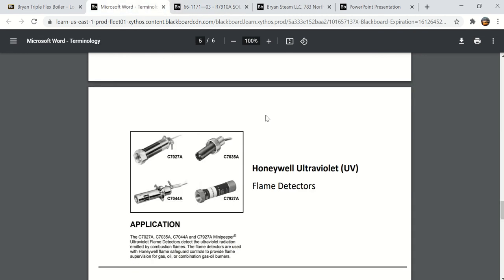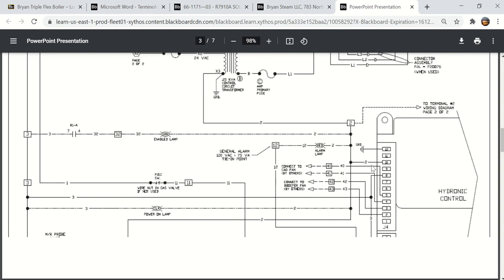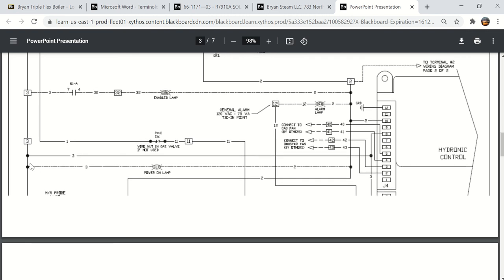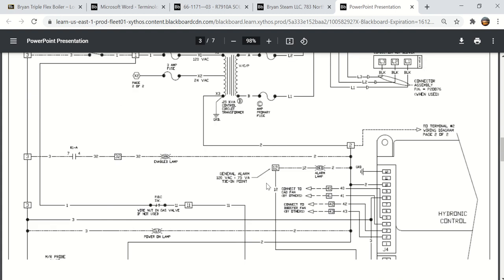All right, getting back to the drawing. There we go. Now I think we've covered pretty much everything that's connected to J4. We have our neutral, we have our ground, we have the power going in here for the UV, and then we have our switch connections here for the combustion air damper and the booster fan. Going on down, here's the power on lamp, which is a clear lamp. Just means that we've got the power turned on. Obviously, if we have power on terminal 3, we've turned on the control switch there.